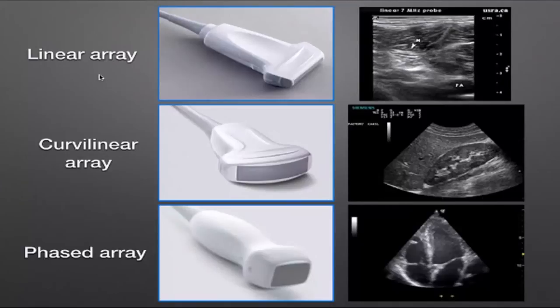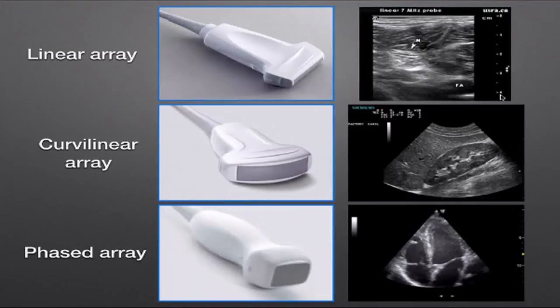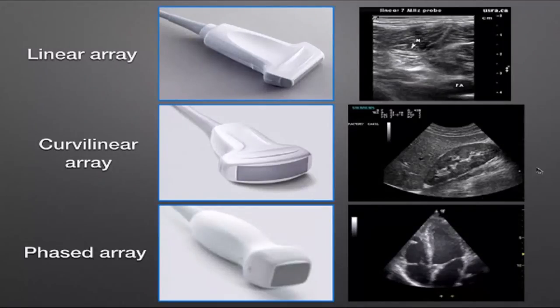The different transducer types include: the linear array, which has a 3–4 cm by 1 cm footplate, sends beams in a straight linear pattern, has a higher frequency, and images to about 4–6 cm depth. The curvilinear array has a larger footplate of about 7 cm by 2 cm, produces a curved sector, and images to 20–25 cm depth because of its lower frequency.